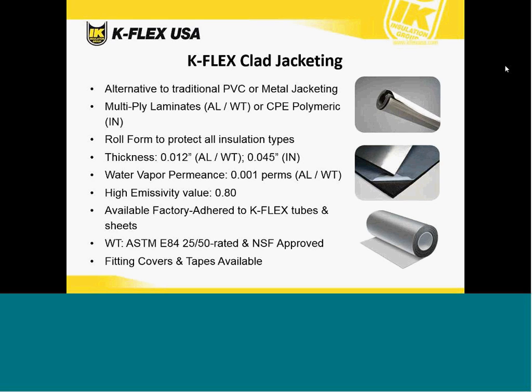Our multi-laminate thickness is 0.012 inches for our clad AL and clad WT, or 0.045 inches for the clad IN. The vapor permeance is 0.001 perms. It's got a very high emissivity value of 0.8, and it's available as an option factory adhered to K-Flex tubes and sheets, so you get a single-step installation process.